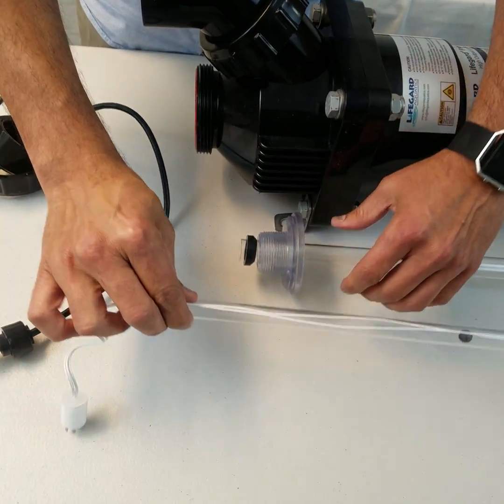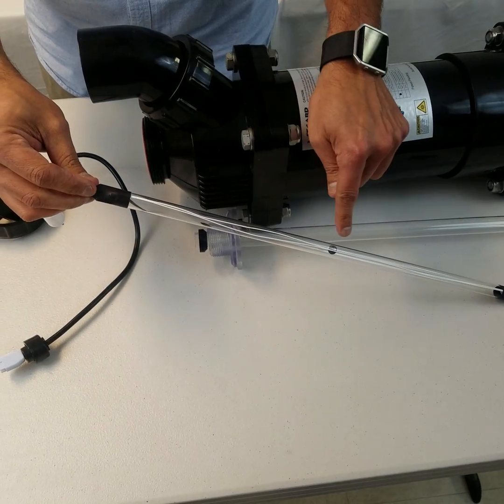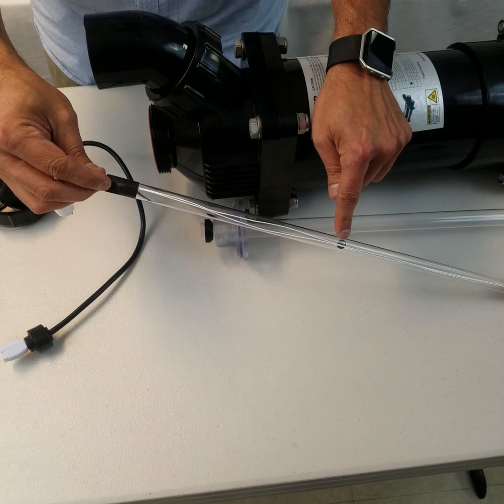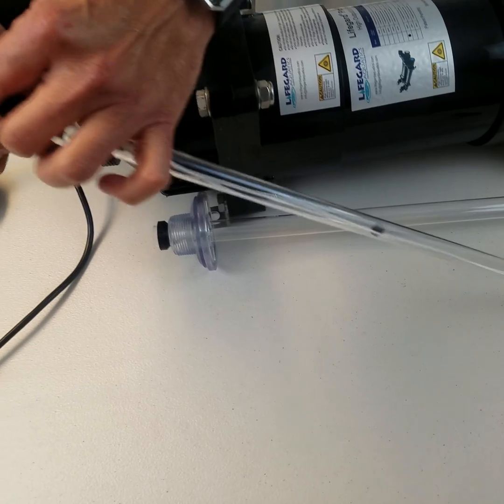Then once this is done, you take the bulb, the UV quartz bulb. The little red dot, the mercury dot, shows that it's an amalgam bulb. So this is a 55 watt UV that we are installing.